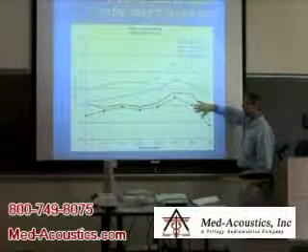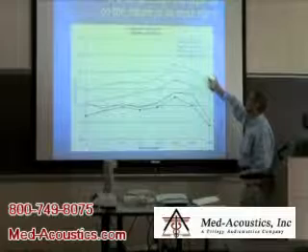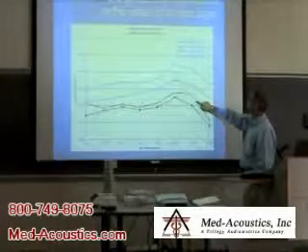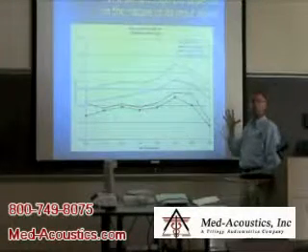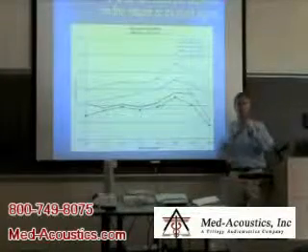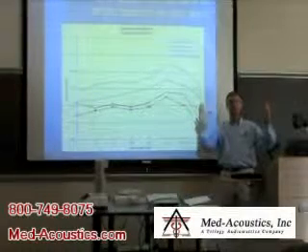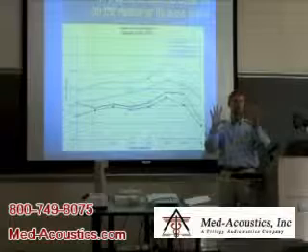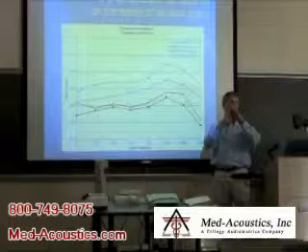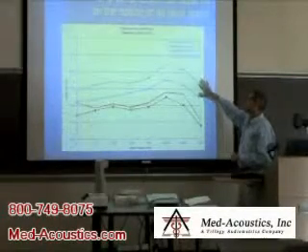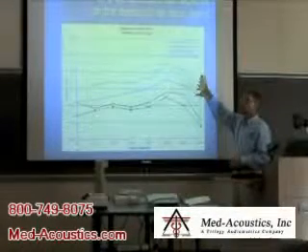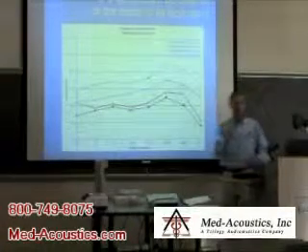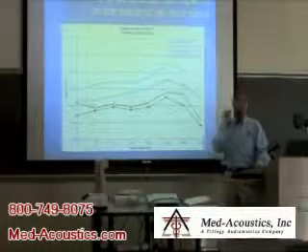The hearing aid is producing four drastically different outputs. One is a pure tone, one is speech-weighted noise, one is speech itself, and one is composite noise. Composite noise is a broadband noise - not frequency specific - covering a wide range of frequencies, typically created by combining many pure tones and modulating them together. The difference exists because this is a digital hearing aid; a linear hearing aid would respond the same regardless of input.